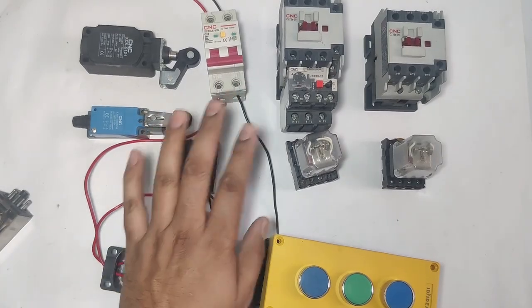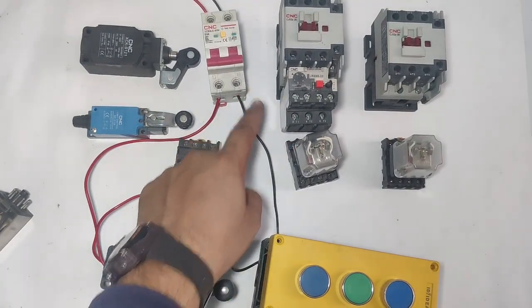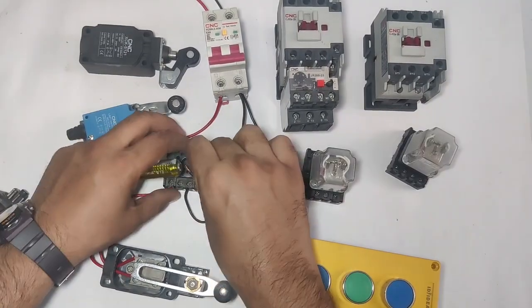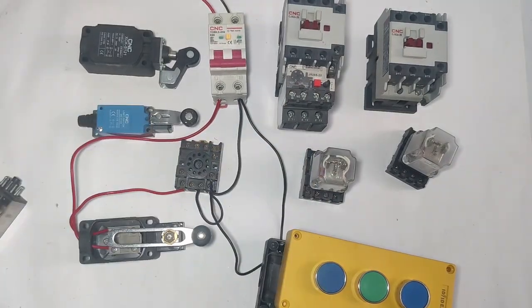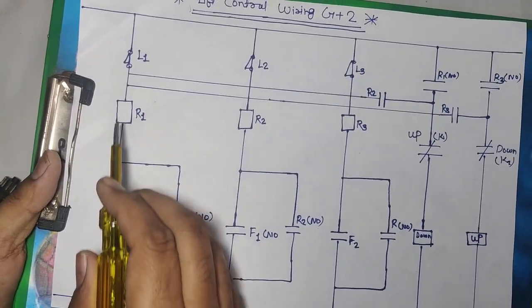One connector connects to the relay common pin 1. We use R1 relay NO point (pin 3) for holding supply. If you connect an emergency push button, take the supply after the emergency output; otherwise take holding supply directly from MCB. So holding connects directly to relay common and the NO point (pin 3). Holding supply is done.